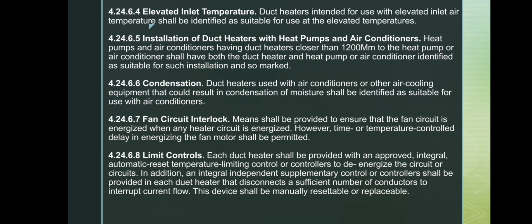Next slide. Duct heaters designed for higher inlet air temperatures must be marked as suitable for that use. When duct heaters are installed near heat pumps or air conditioners closer than 1200 mm, both the heater and the HVAC equipment must be identified as compatible.